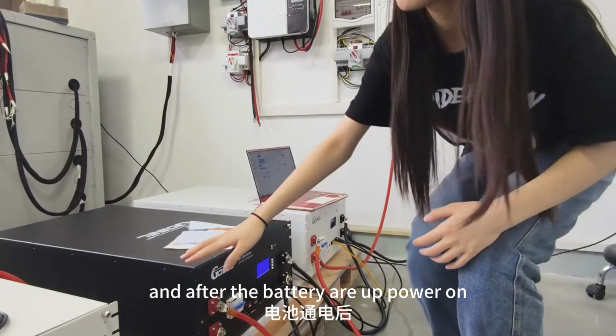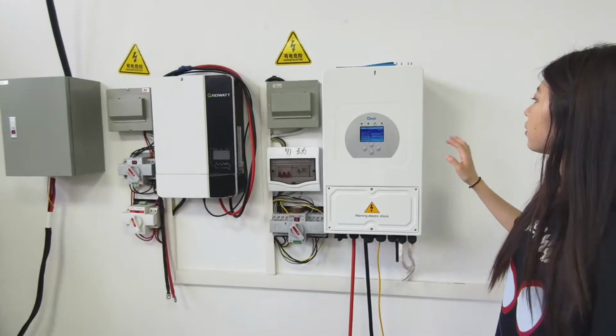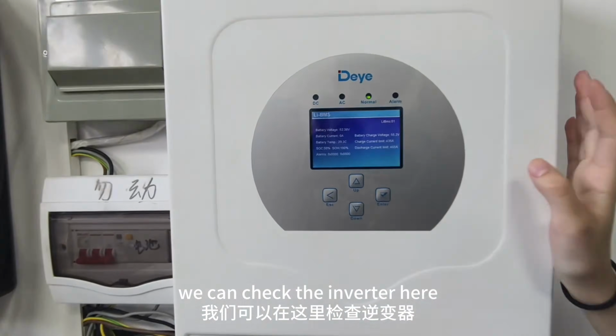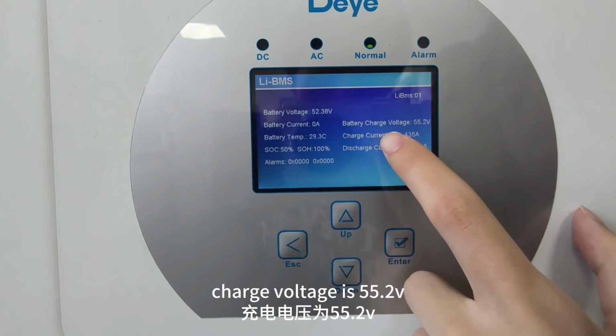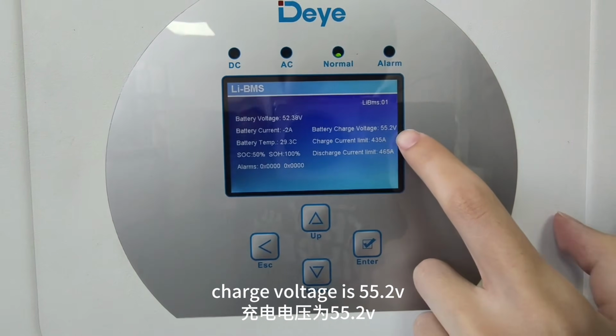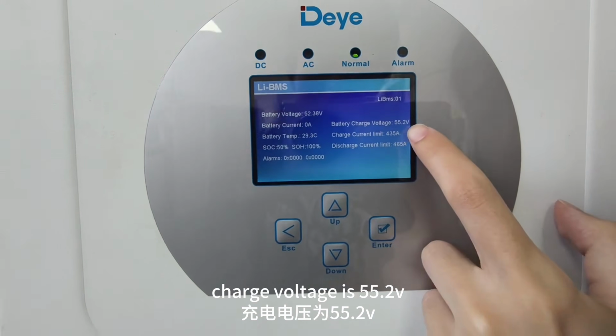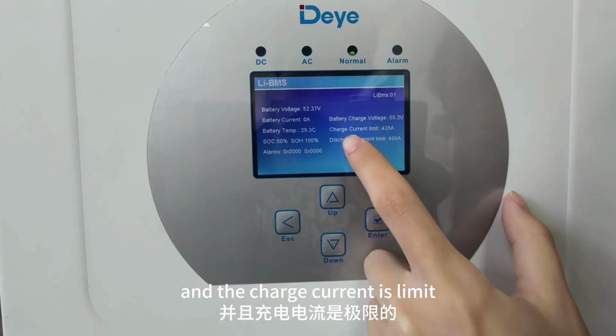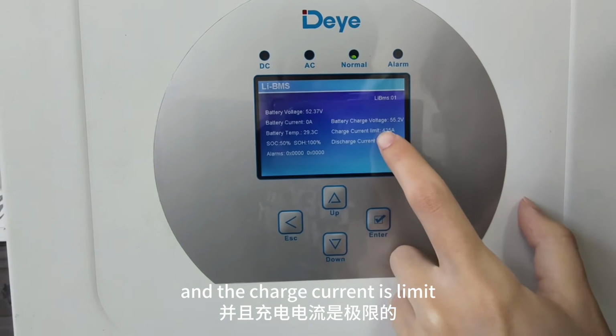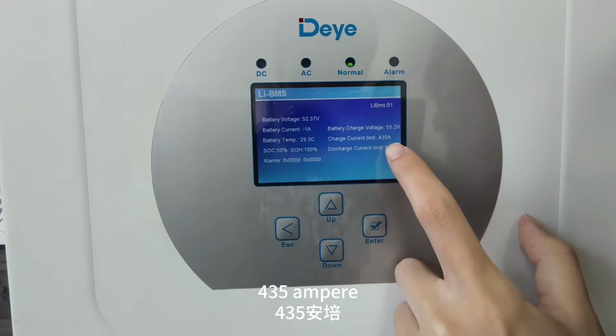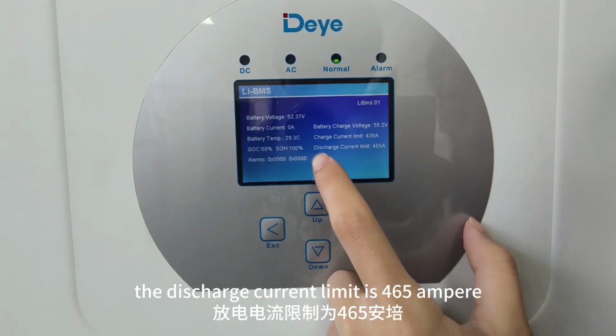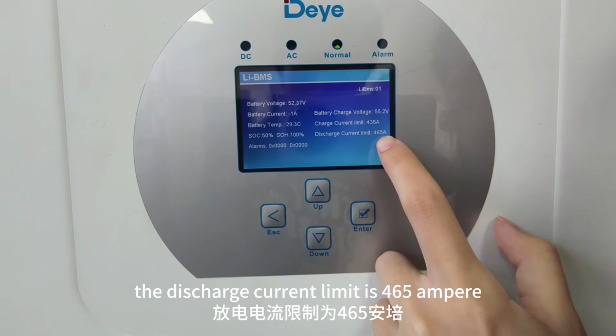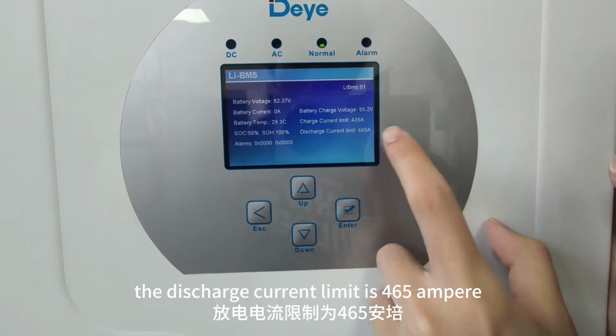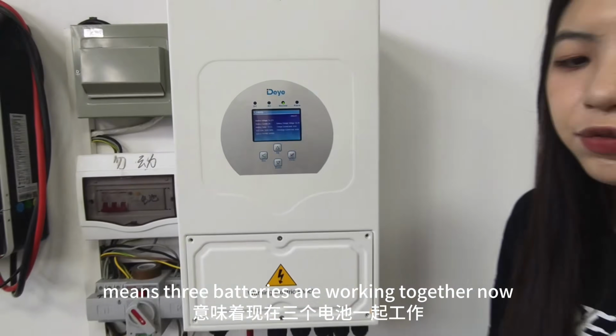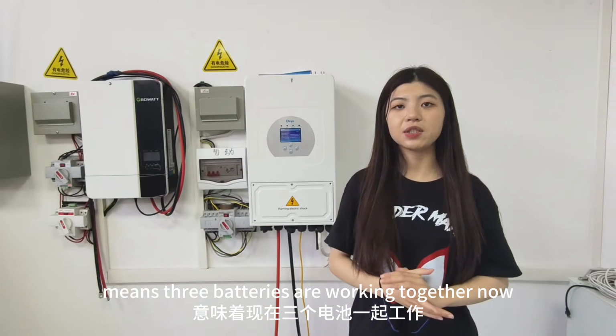After the batteries are powered on, we can check the inverter here. We can see the battery charge voltage is 55.2 volts, and the charge current limit is 435 ampere. The discharge current limit is 465 ampere, meaning 3 batteries are working together now.